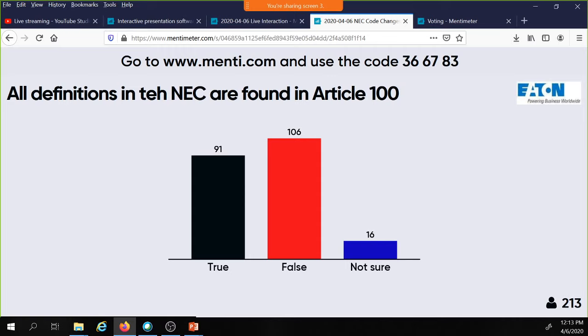But you can't just look in Article 100. You also have to look in each article to see if there are any terms used there. And if there's a term used in the National Electrical Code that you cannot find defined, the fallback position is Webster. Merriam-Webster is the official reference for terminology used in the NEC when it's not defined there. But also keep an eye on the building code, since your other codes could drive those definitions too.